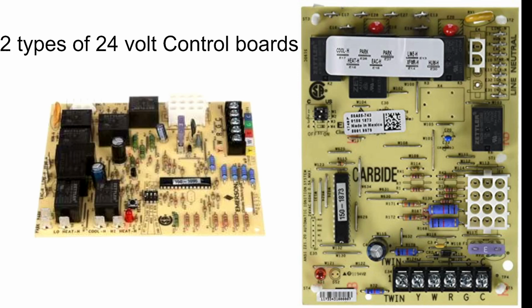And even on, if you look at the right-hand corner, if you look at the top, you'll see where it says cool and park and heat, EAC, another park lines. You'll have one for humidifiers. This board actually has connections if you have a dehumidifier that's connected to your gas furnace or your air handler. It can plug into your control board and be controlled from that function. That means it won't kick on until you call for heat or cool.